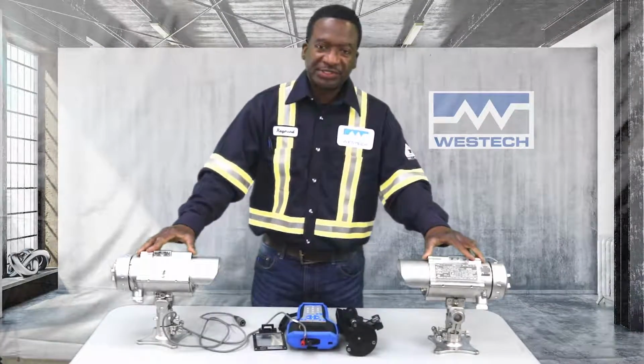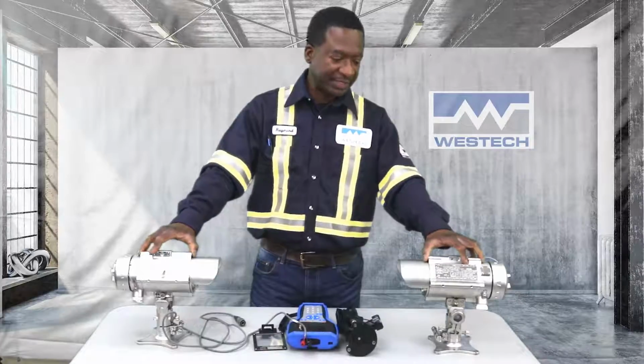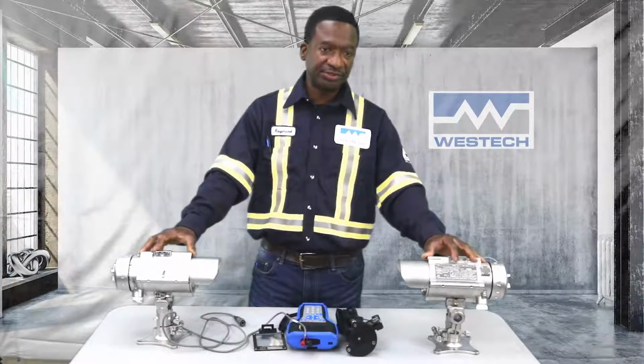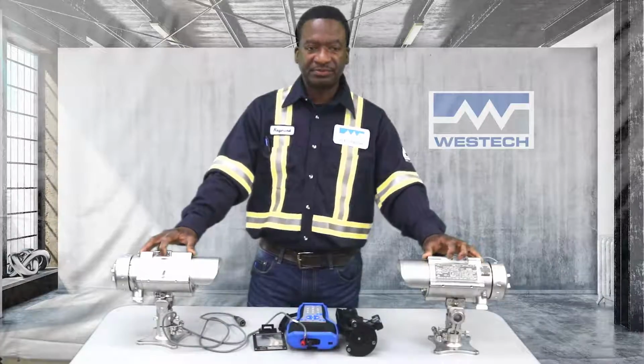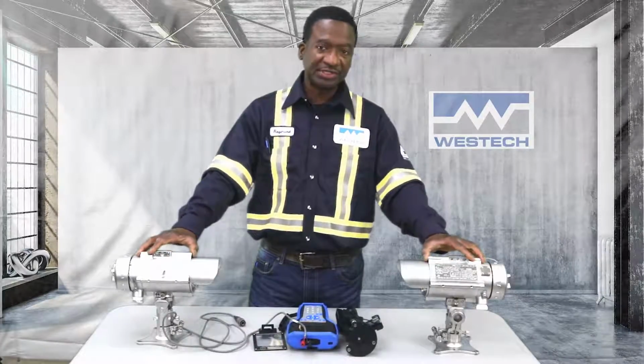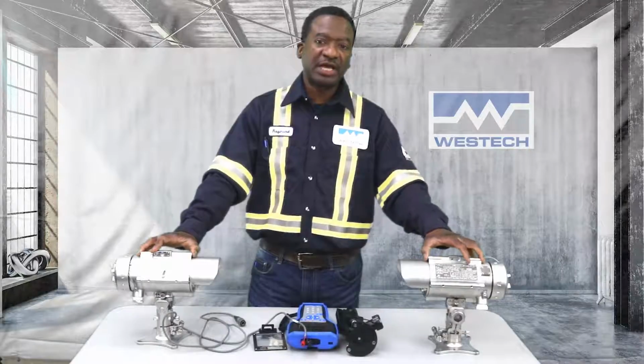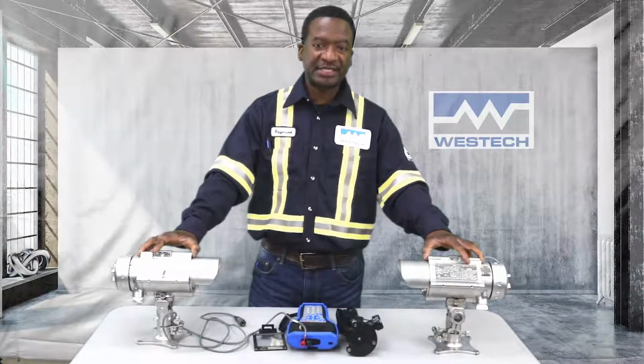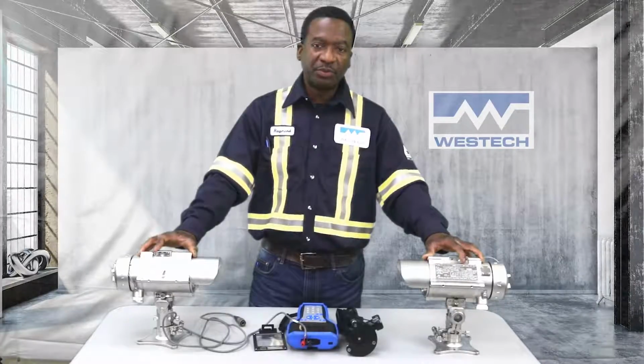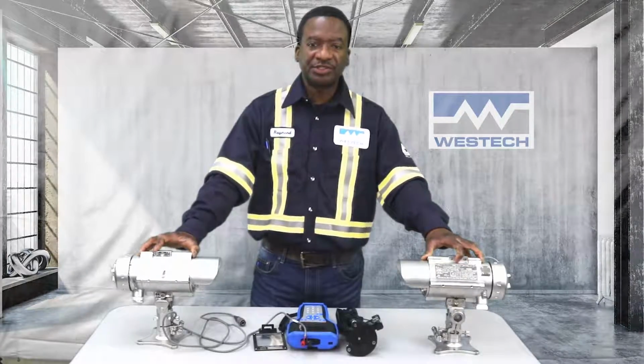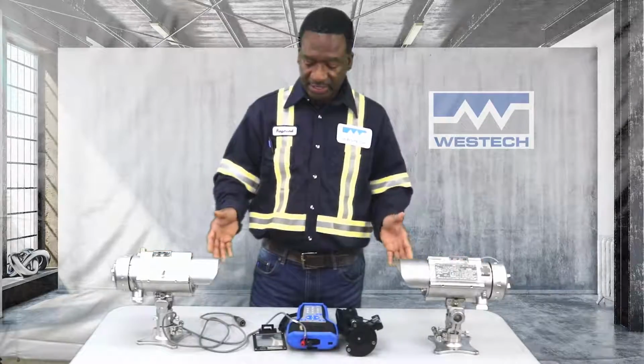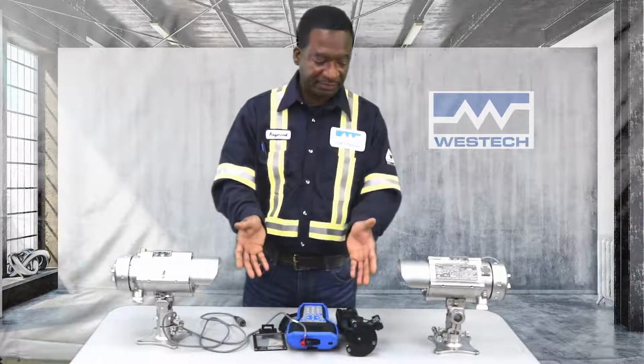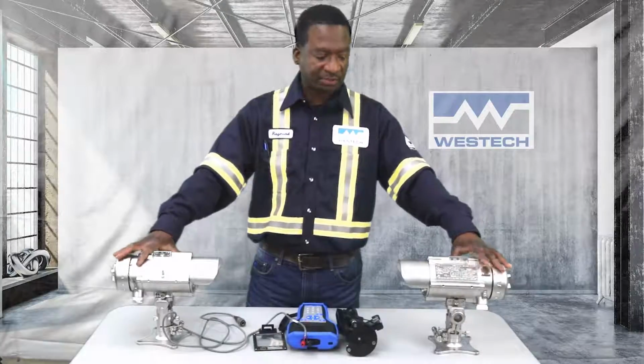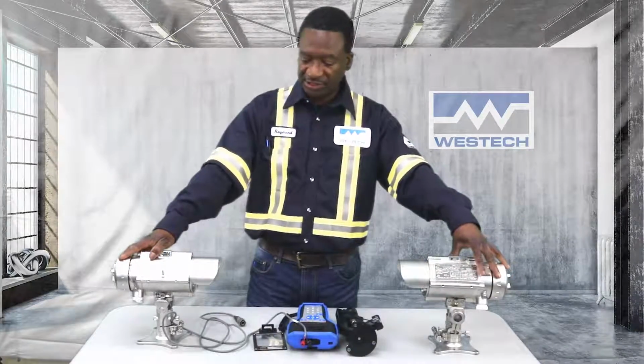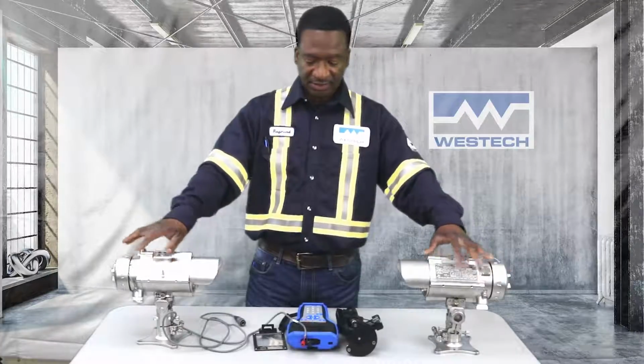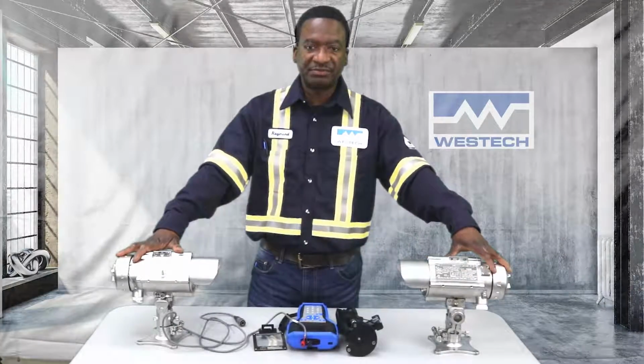One of the frequently asked questions is, why choose an open path detection system over a traditional point detection system? Well, one of the main reasons is, point detection systems rely on the accumulation of gas at the sensor. An open path detection system does not rely on the accumulation of gas, as long as the gas cloud cuts across the path of the beam, taking into consideration, of course, the placement and positioning of the receiver and transmitter and a clear line of sight of the detection system.